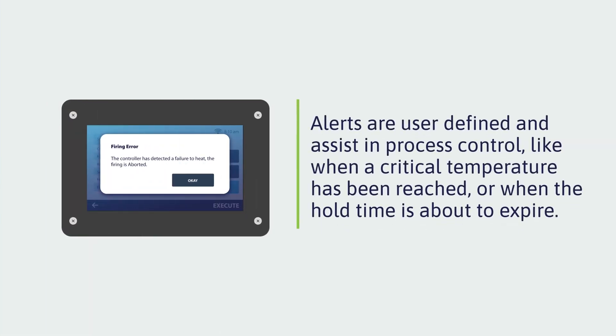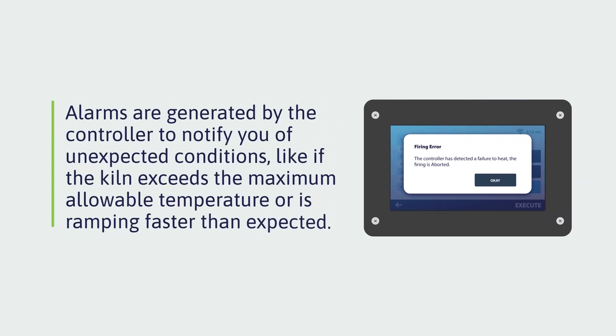Alerts are user-defined and assist in process control, like when a critical temperature has been reached or when the hold time is about to expire. Alarms are generated by the controller to notify of unexpected conditions, like exceeding the maximum allowable kiln temperature or the kiln ramping faster than expected.